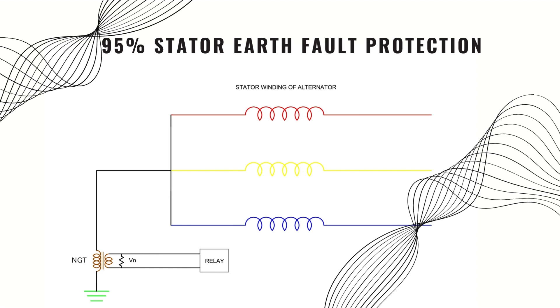In the 95% stator earth fault method, the relay continuously monitors the voltage across the resistor connected to the secondary terminal of the NGT. When the voltage exceeds the predetermined value, the relay senses an earth fault occurred in 95% portion of the stator and trips the generator. Let's understand how this logic works.